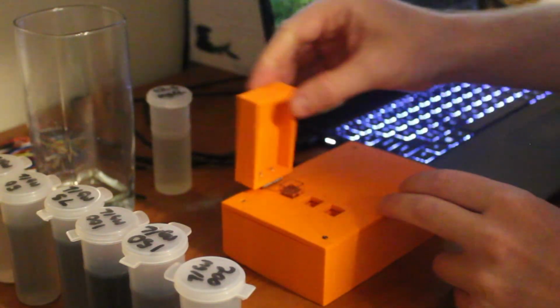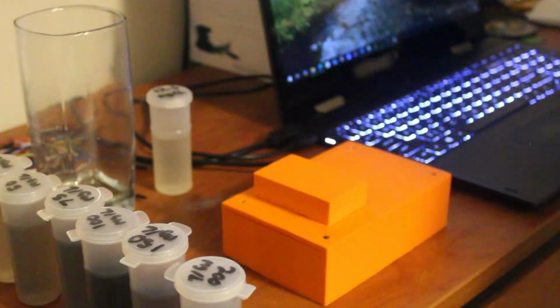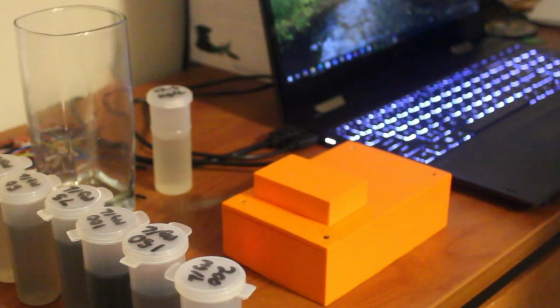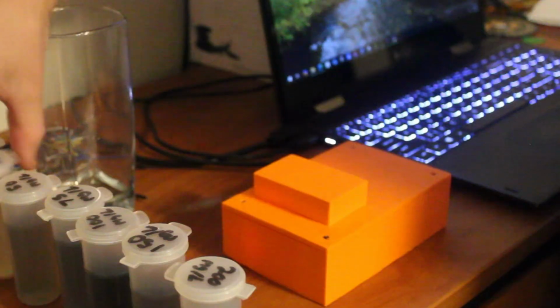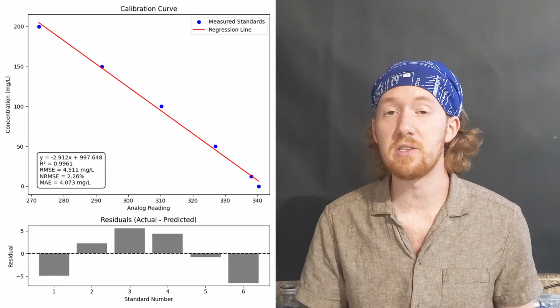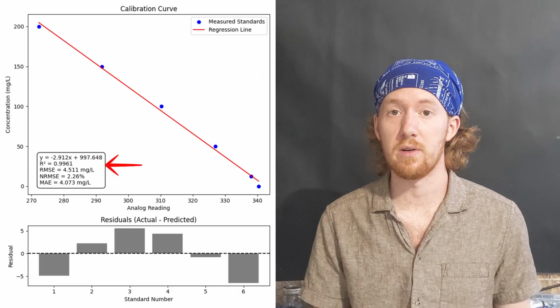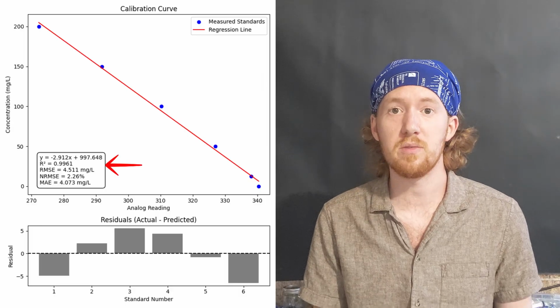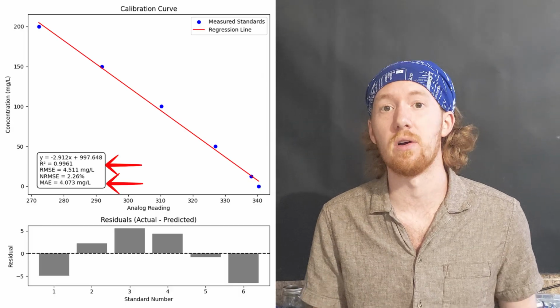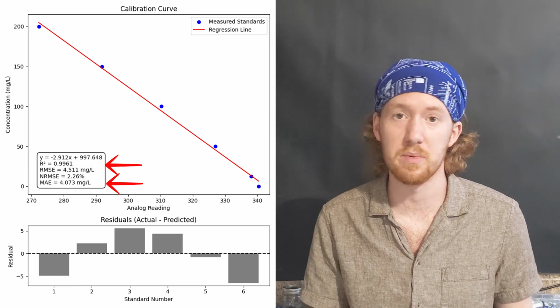This will run for about 15 seconds and take an average of those 15 measurements taken once per second. So I'll go ahead and do this for all 6 samples, and then we can discuss the results. So I am happy to confirm that the calibration was a success. In the results here, we can see that we got a high R squared of 0.99, as well as a relatively low mean absolute error of 4.07 milligrams per liter.